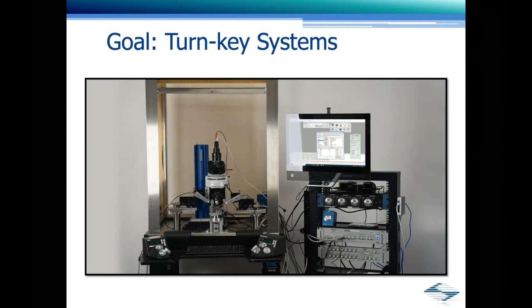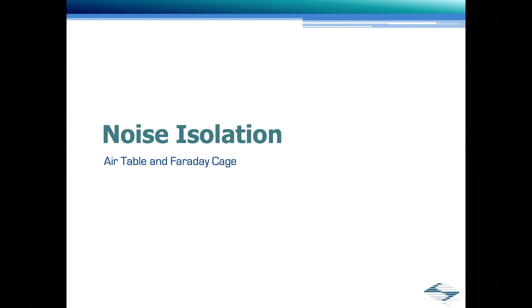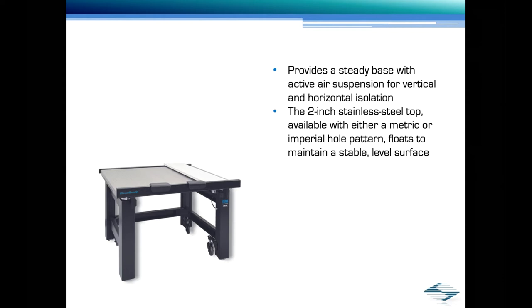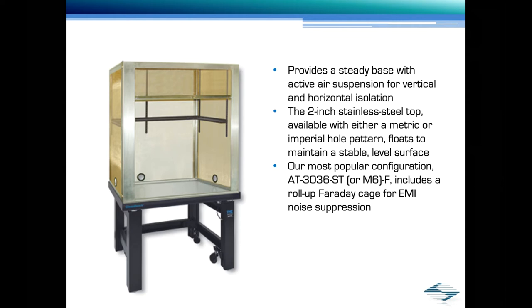Electrophysiological recordings are highly susceptible to environmental factors that introduce noise to the signals. Predominant noise sources are mechanical vibration and electromagnetic interference. Sutter offers a series of vibration isolation tables and accessories from TMC Vibration Control that provide the foundation for the rig. Each table provides a steady base with active air suspension for vertical and horizontal isolation. The 2-inch stainless steel top is available in either metric or imperial hole pattern. Our most popular configuration, the AT3036, is a 30x36 table and includes a roll-up Faraday cage for EMI noise suppression. Optional accessories include casters for making it easier to move the table, padded armrests, and air compressor for those labs that don't have house air.